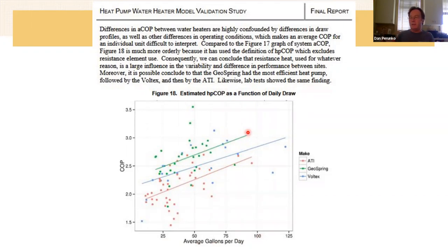And that occurs because the heat pump portion of the water heater is happiest when there's a bigger temperature difference between the water and the refrigerant. So cold water getting heated is more efficient than warm water getting heated. So they build the tanks so that they're stratified on purpose: cold water at the bottom, hot water at the top. Cold water gets heated and then returned to the top of the tank where it's hot. And so this relationship is very durable. The more water that you heat, the more cold water you put in the bottom, the more efficient the system is.